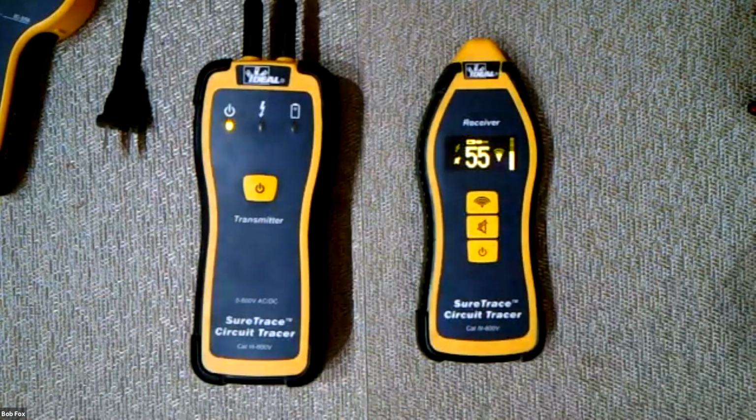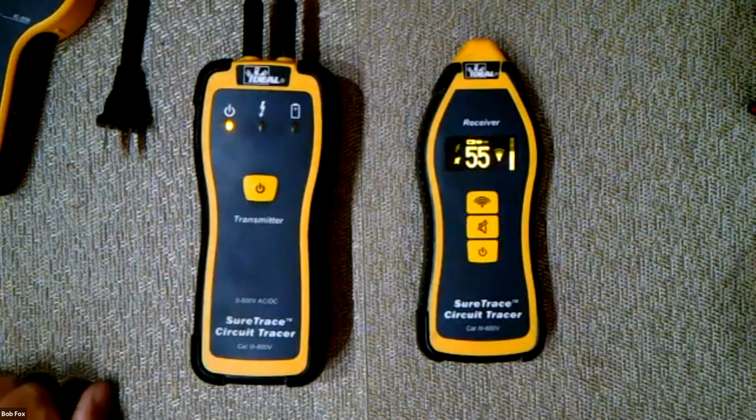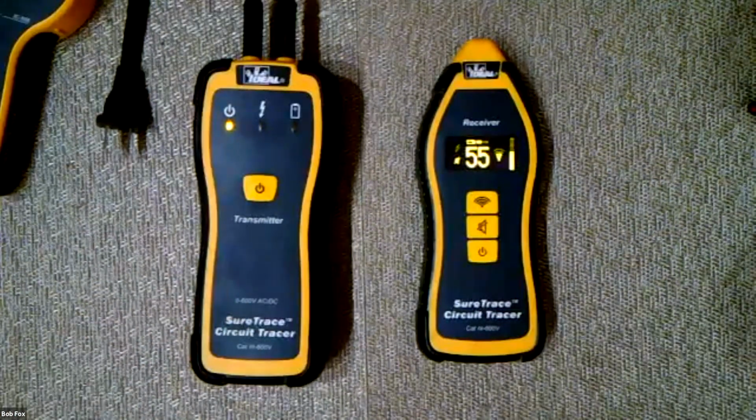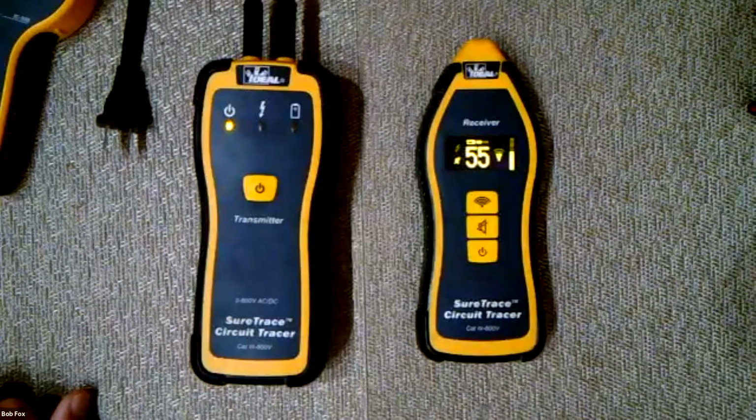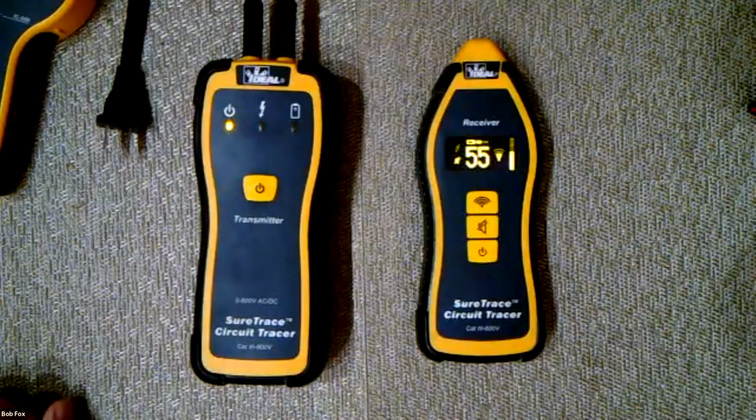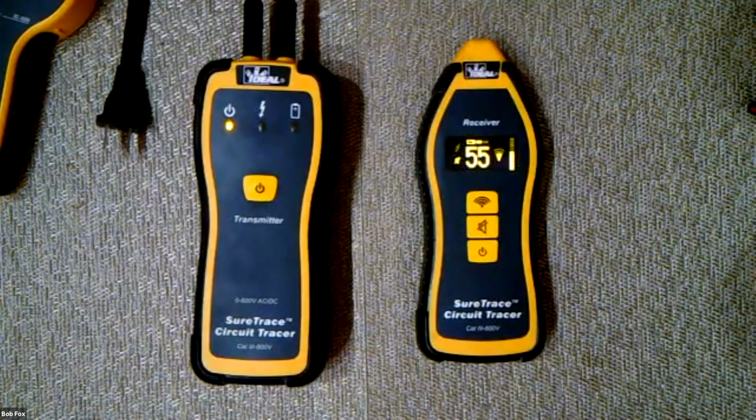People often ask too, can I just put the signal onto the shield itself, whether it's a datacom cable or MC? Well, you have to be careful, because people often put it from hot to ground. And once you put it on the ground, you basically found the building. The signal goes everywhere and it becomes confusing. So there are all kinds of techniques, some of which are covered in the video, and some of which we encourage anybody to call in about and say, I have this application or I'm trying to do this, and we help you through it as best we can.